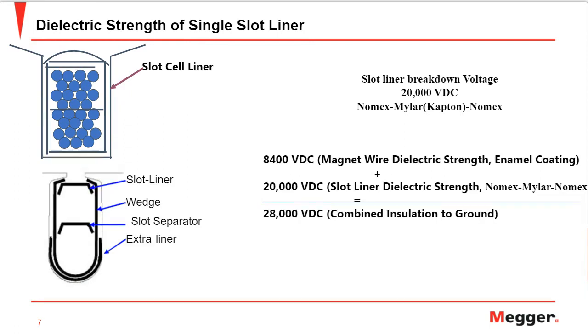Out of those 28,000 volts, 8,400 volt DC is the enamel coating on the copper wire, and the remaining 20,000 volt DC is the slot liner dielectric strength, which usually consists of a sandwich of materials like Nomex, Mylar, and Nomex, and sometimes Mylar can be replaced by Kapton. These insulation materials have a pretty high dielectric strength. For example, Nomex can withstand electric stresses of up to 18 to 34 kV per mm.